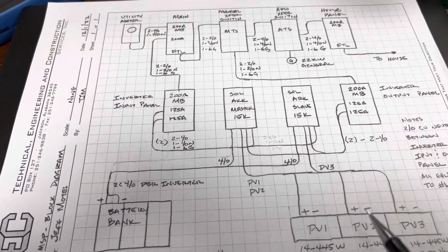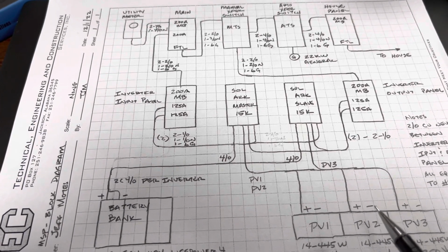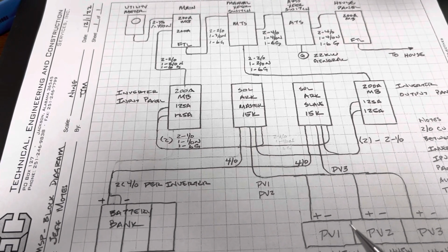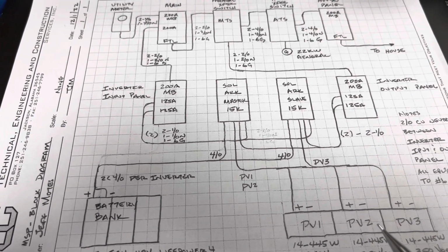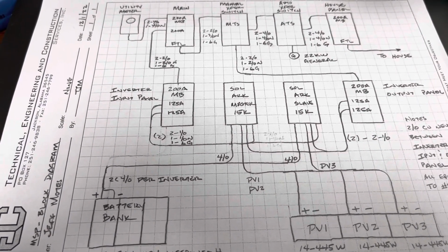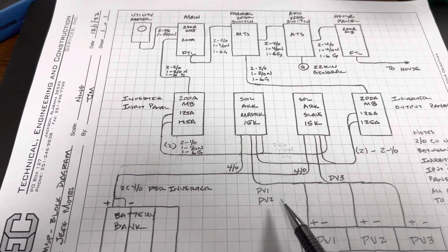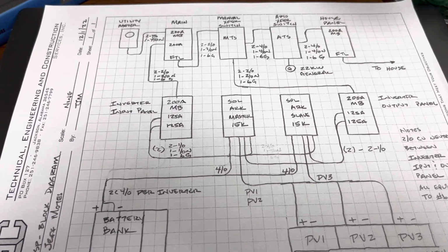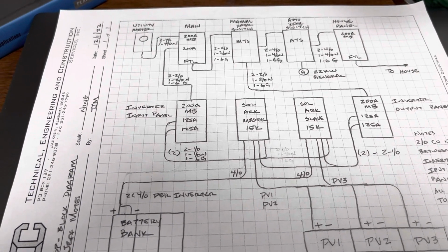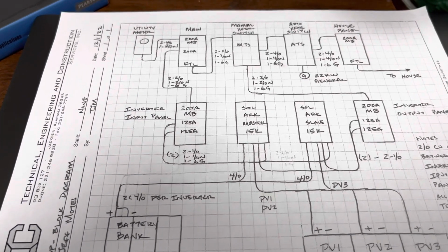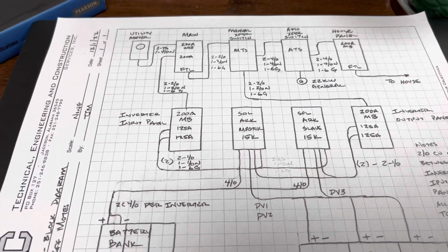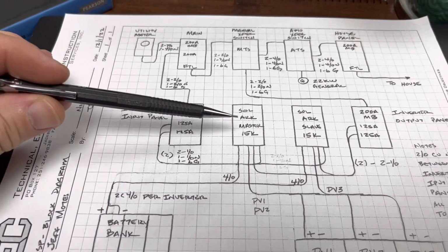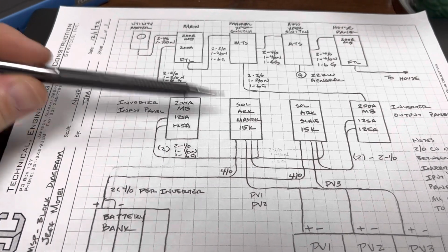So that's my second power source coming into the inverters. I'm using number 10 PV wire at the array, number 4 aluminum in the ground. And then when I come out of the ground and hit the disconnect box on the outside of my C-can, my metal building, I transition back to number 10 copper, and that's what comes in to each of the Sol-arks.